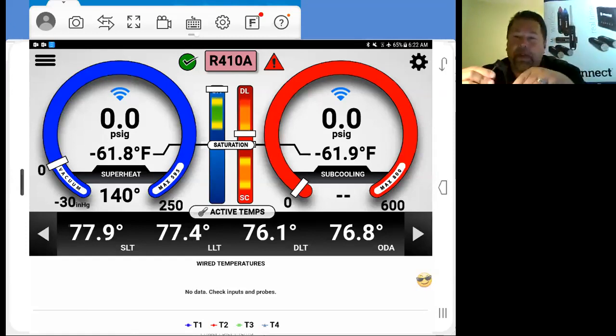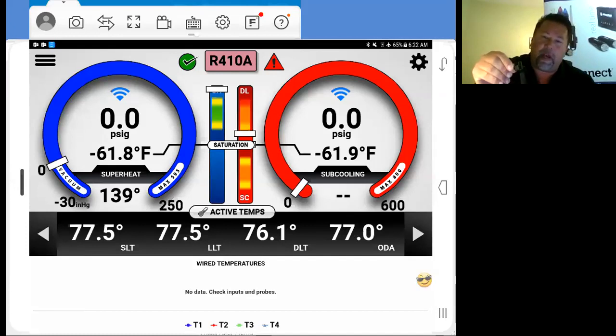Now on these thermistors here, you'll see that they're black when you get them. Over time, this little black coating will start coming off. Don't worry about that. That's not trashing the sensor or anything else. But when you do have a dirty piece of pipe, do not put the sensor up on top and wrench it around thinking that you're going to get a better connection. Clean the piece of pipe off.